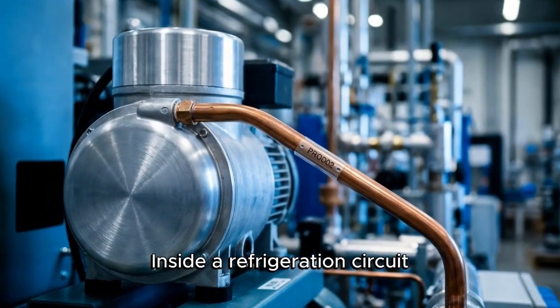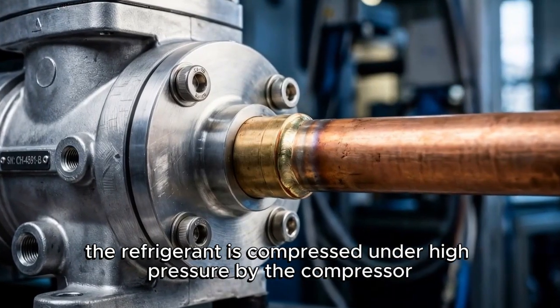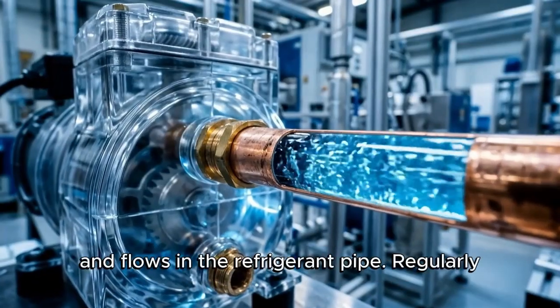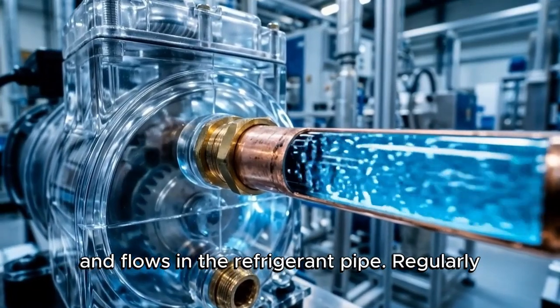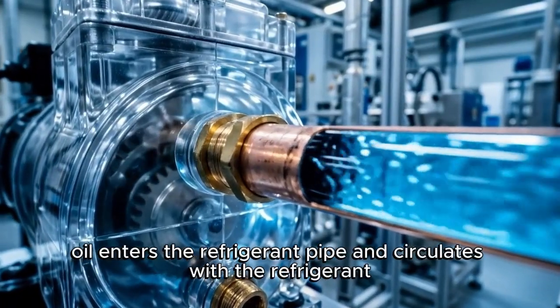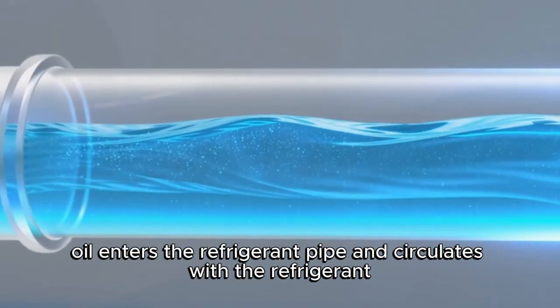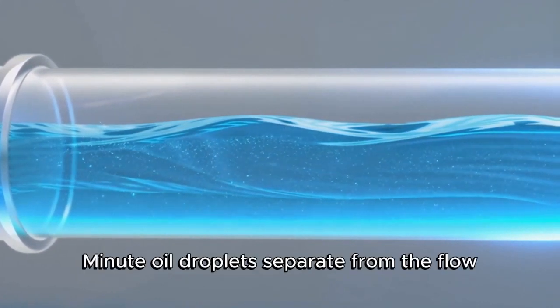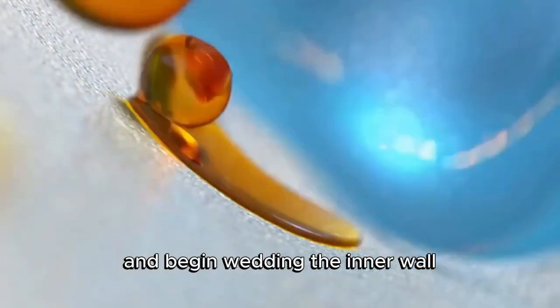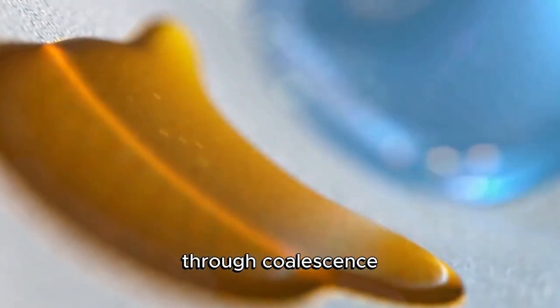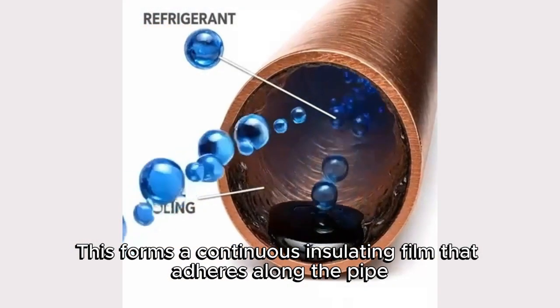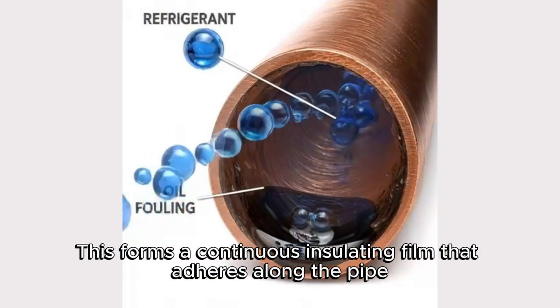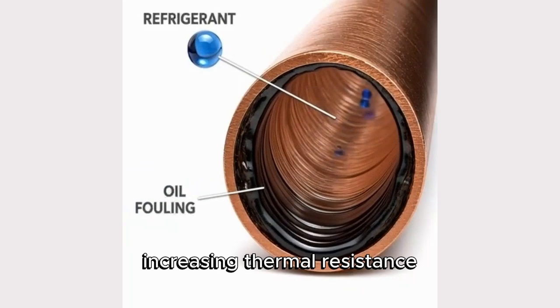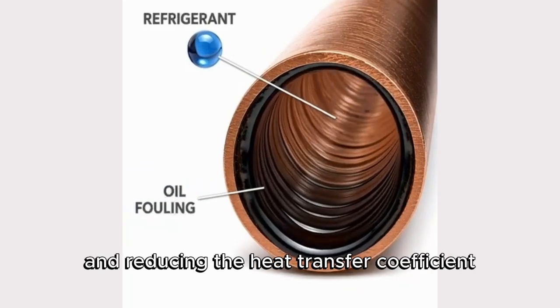Inside a refrigeration circuit, the refrigerant is compressed under high pressure by the compressor and flows in the refrigerant pipe. Regularly, the compressor oil enters the refrigerant pipe and circulates with the refrigerant. Minute oil droplets separate from the flow and begin wetting the inner wall through coalescence. This forms a continuous insulating film that adheres along the pipe, increasing thermal resistance and reducing the heat transfer coefficient.